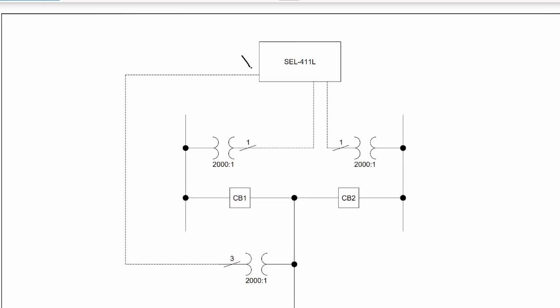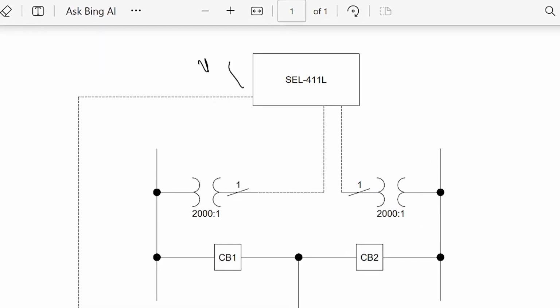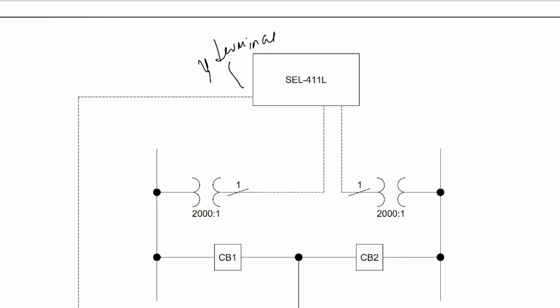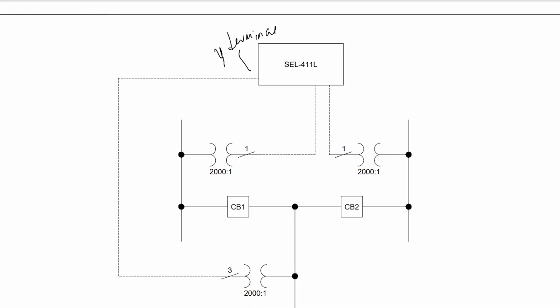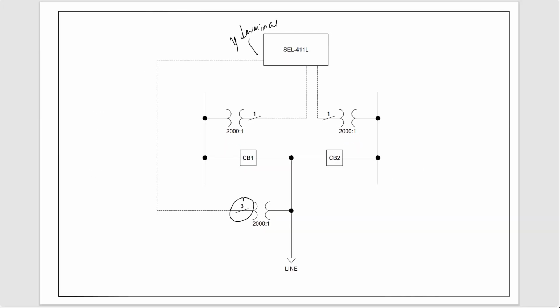So this over here would be the Y terminal, meaning it's going to be the VAY, VBY, and VCY connections on the relay. And as you can see over here, that's a three-phase connection. And we also have the PT ratio over here, which is 2000 to 1, which is typical for a 230 kV line. Now we'll also assume that the bus voltages are connected to the Z terminals of the relay.